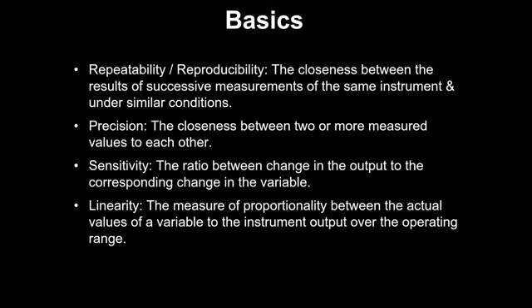Then basically the linearity. Linearity is the proportionality of the signal output with respect to the change in the variable. Suppose the temperature goes up from 100 degrees to 200 degrees, so it is doubled. Is the signal from the sensor also doubled, or does it change in some other proportion? That is the linearity. And for accuracy and for better reading, it should be linear. If the change is proportional to the square or some other odd value, or the correlation is not linear, it becomes more complicated to get the correct reading. So most instruments will be selected to operate in the range where the relation is linear.